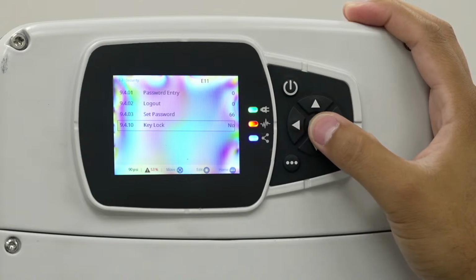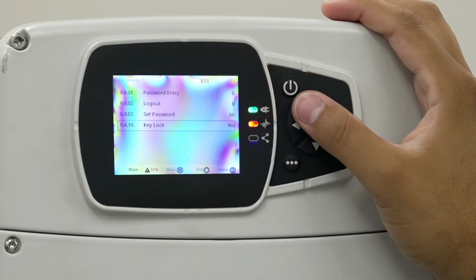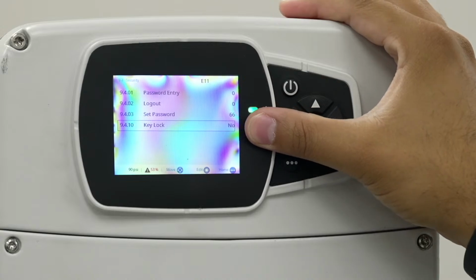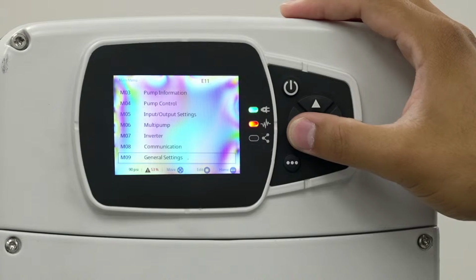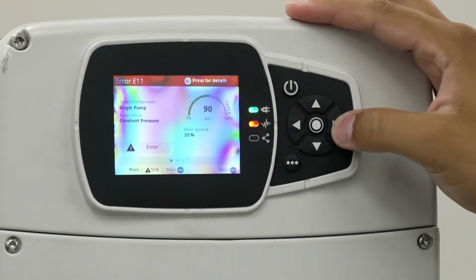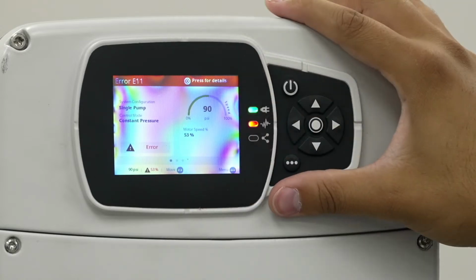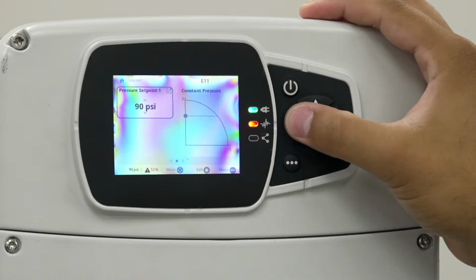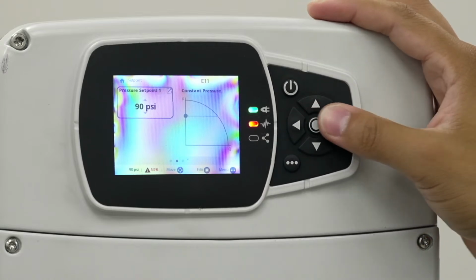Key lock, you can tell what the password does. So right now it's just to simply get into the main menu group, but this key lock, right now it says no. You can change that to yes, so then they can't even navigate. If they were back on the home screens, they wouldn't be able to navigate even between these and adjust these. So it's just giving you a little bit further password protection on the unit, because right now it's strictly just to the menu group, but ideally, you may still want it at this stage where people can't come up and press or change anything.